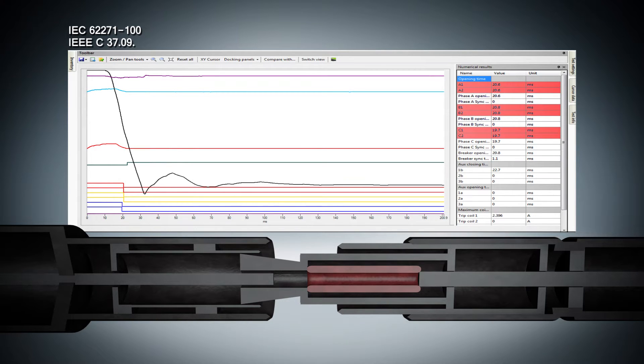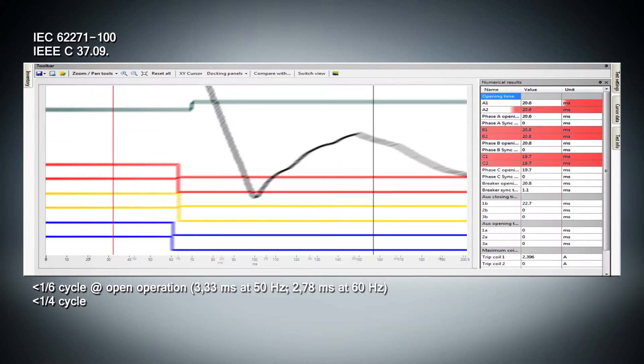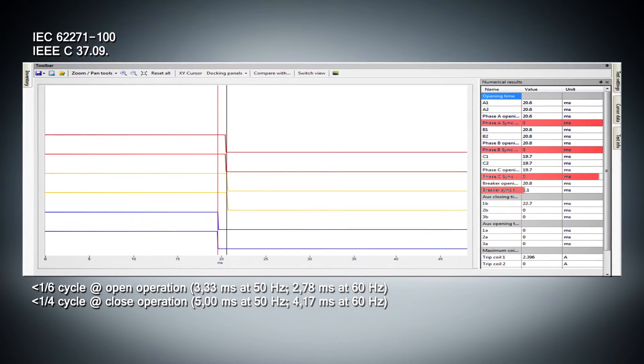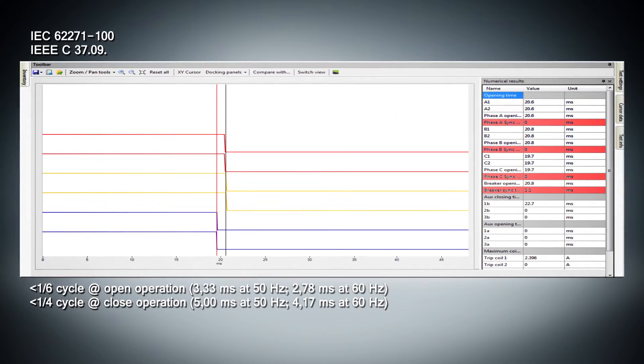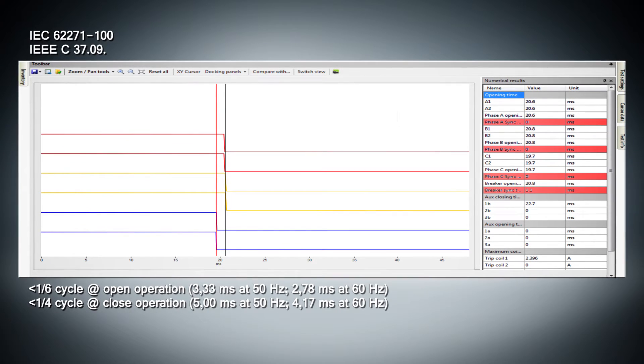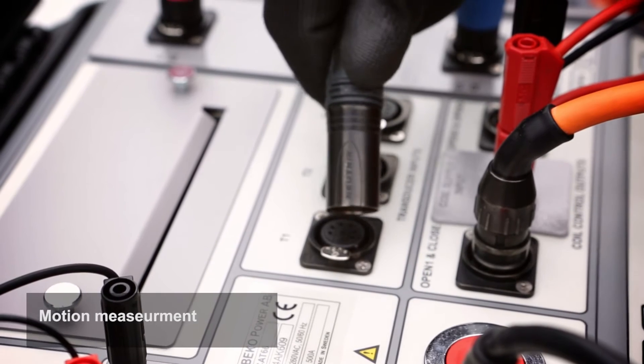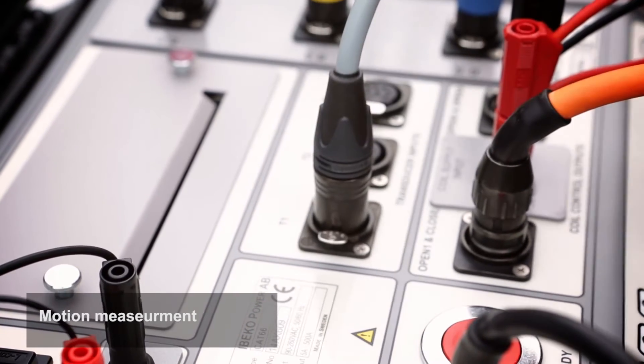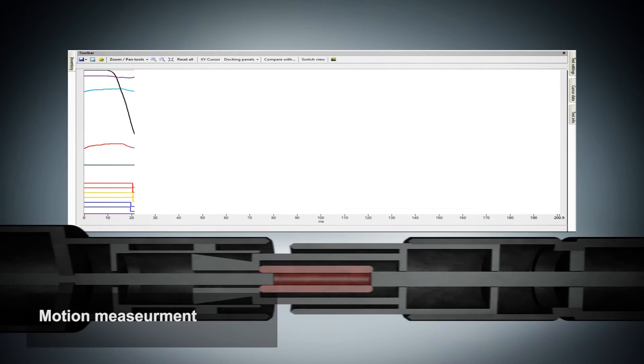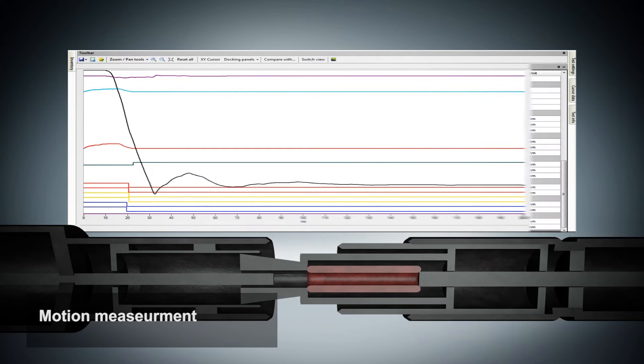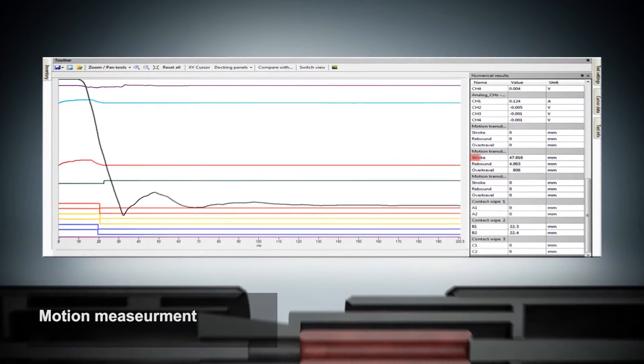Synchronization between the circuit breaker poles has to be within specified limits. Simultaneous measurements within a single phase are important in situations where a number of contacts are connected in series. The free transducer channels are intended for measuring displacement of the circuit breaker moving parts, contact wipe, over travel, rebounds, damping time and average velocity.